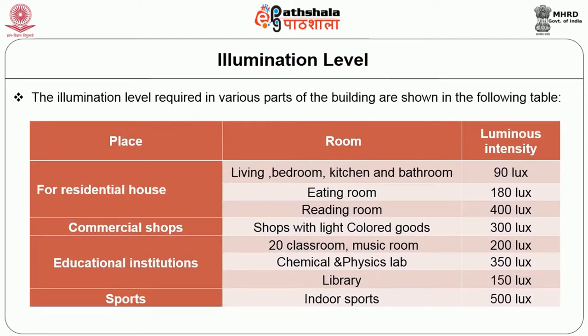The illumination levels required in various parts of a building are shown in a table. For example, for a residential house, the living room, bedroom, kitchen and bathroom need 90 lux. For indoor sports, 500 lux is required. For educational institutions such as a library, 150 lux is needed.